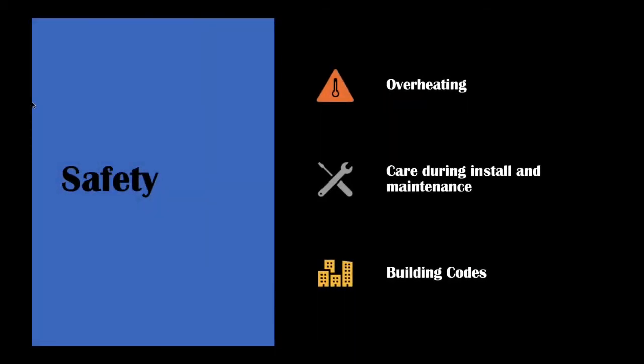Due to the sealed vacuum within their design, evacuated tube collectors can get very hot, exceeding the boiling point of water during the hot summer months. These high temperatures can cause significant issues in an existing solar hot water system, such as overheating and cracking of the evacuated glass tubes. To help prevent this from happening in hot summer climates, bypass valves and large heat exchangers can be used to dump the excessive heat, as well as mixer valves which mix regular water with the hot water to ensure the temperature and pressure levels never exceed a preset limit. Other forms of care and oversight should be utilized when installing or performing maintenance on rooftops, as well as following local building codes and ordinances.